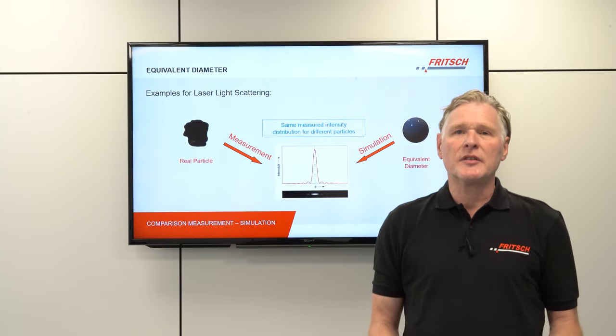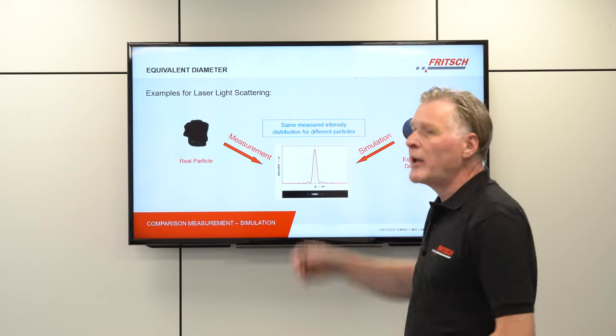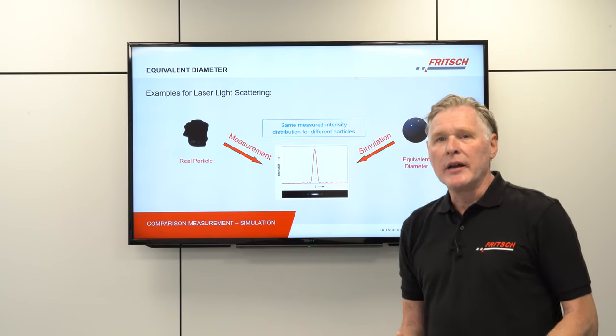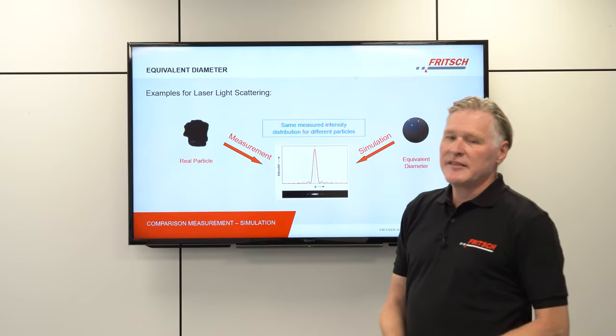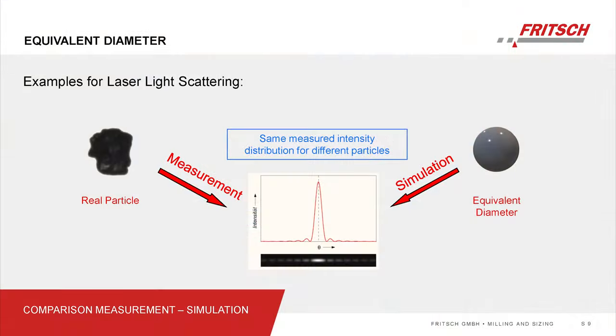Now let's look at what we actually get from our measurement. In laser diffraction, a real particle is illuminated by light and produces an intensity distribution as shown in the center of this image. We perform a simulation, trying to calculate a spherical particle that produces as nearly identical an intensity distribution as what was actually measured. The diameter of this sphere is what we call the equivalent diameter of laser diffraction.